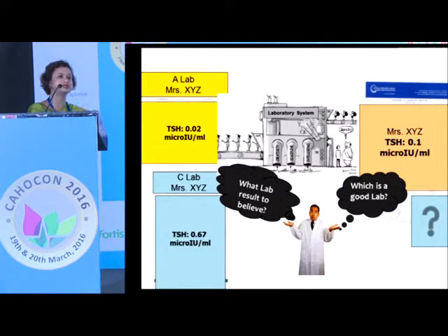When it went to the technical committee, they wrote, because this was for thyroid function test for TSH, that our value was not more than, it was less than 0.95. So how have you accepted as an assessor, how have you closed that non-compliance? Then I had to challenge the NABL technical committee, saying that what you are saying is incorrect, because for TSH we have seen there can be 40% difference or 40% variation between method to method, or between different analyzers. So sometimes it is very important to understand our test, and sometimes if required, we need to challenge the expert.